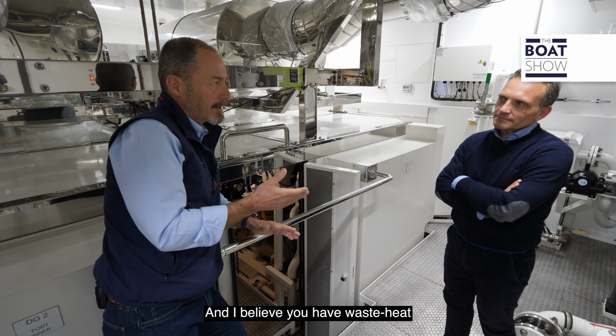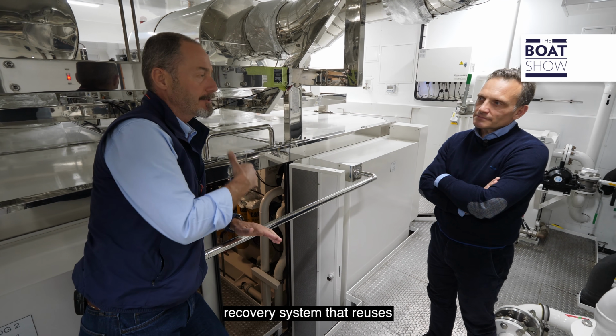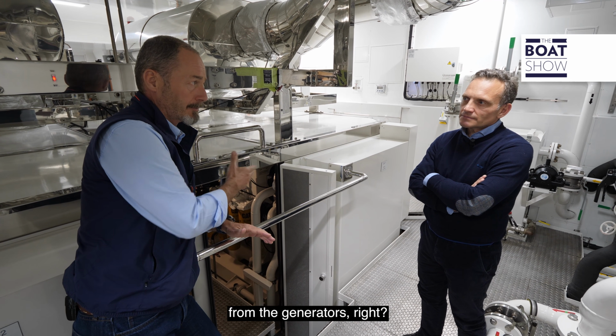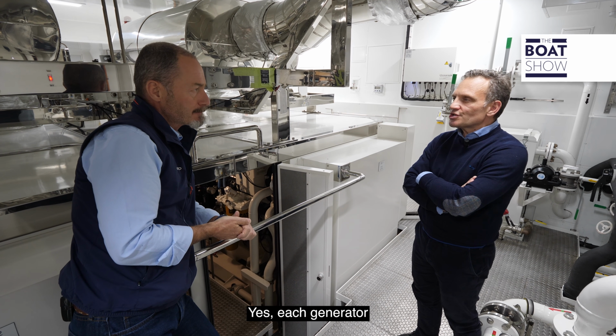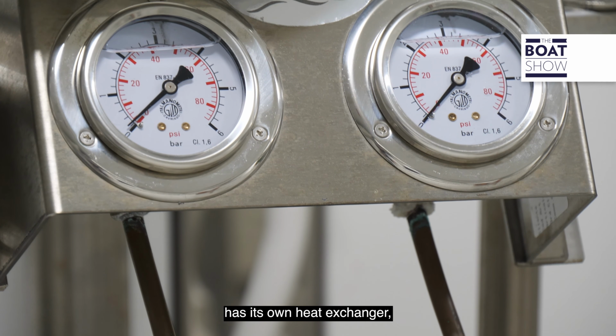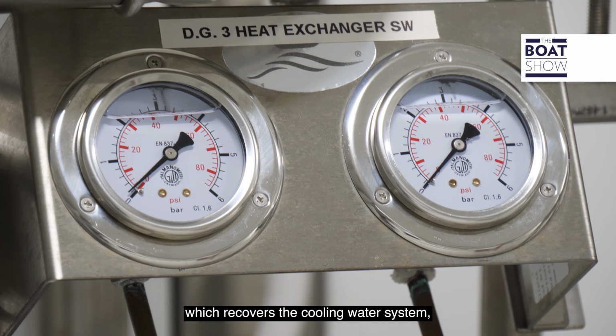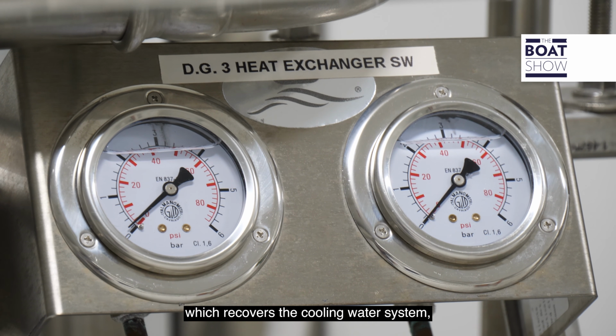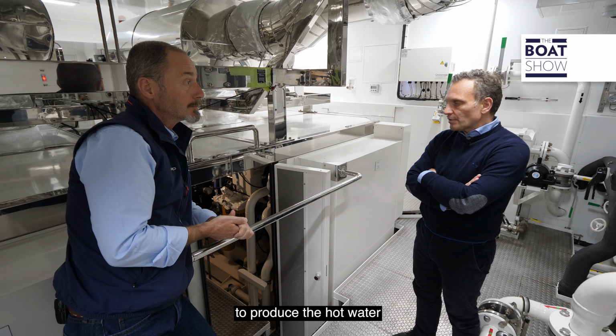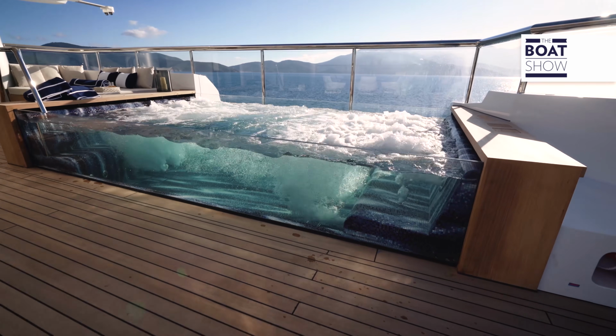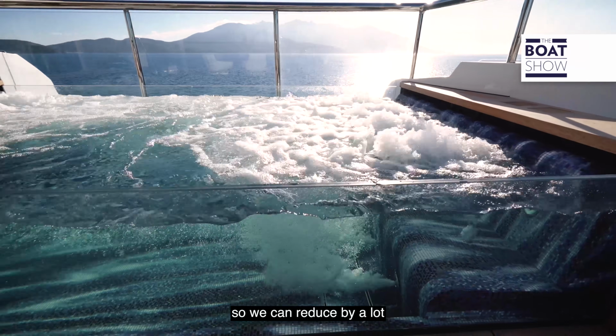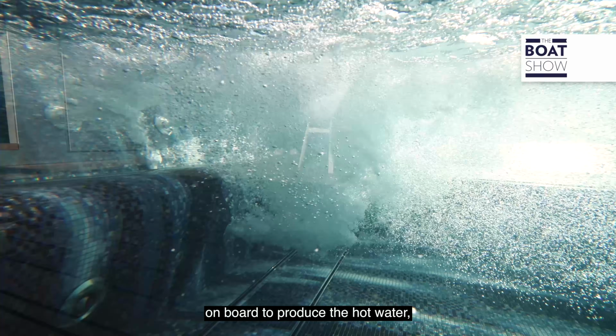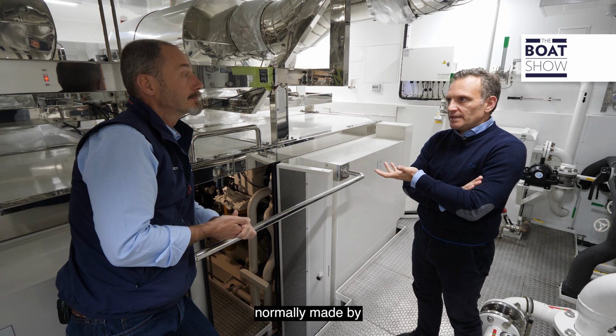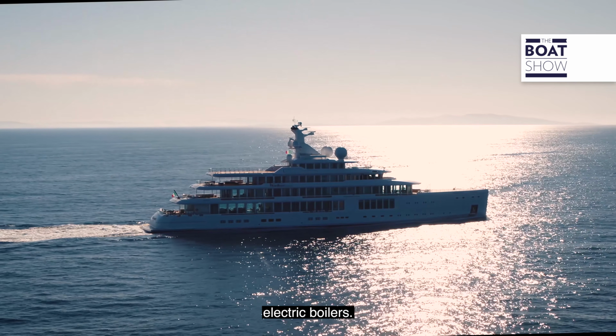And I believe you have a waste heat recovery system that reuses the cooling water from the generators, right? Yes, each generator has its own heat exchanger, which recovers the cooling water from the seawater cooling system to produce hot water, so we can reduce a lot the amount of power on board needed to produce hot water, normally made by electric boilers.